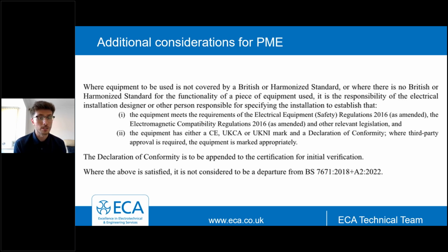Some of the things that the installation designer would have to confirm is that the equipment meets the requirements for the electrical equipment safety regulations, the electromagnetic compatibility regulations, and any other relevant legislation. Additionally, the equipment should have either a CE, UKCA, or UKNI mark, and importantly, a declaration of conformity should be available. So this declaration of conformity is required to be appended to the certification as part of the initial verification process.